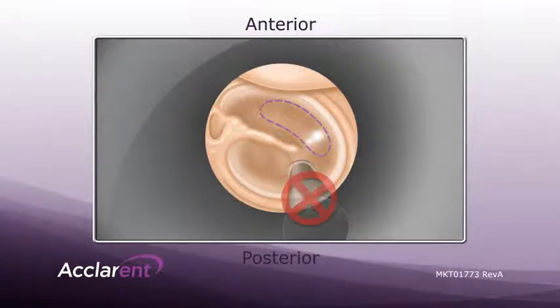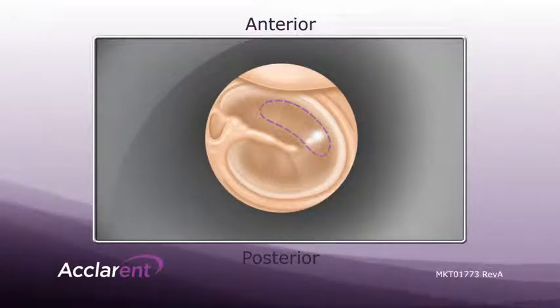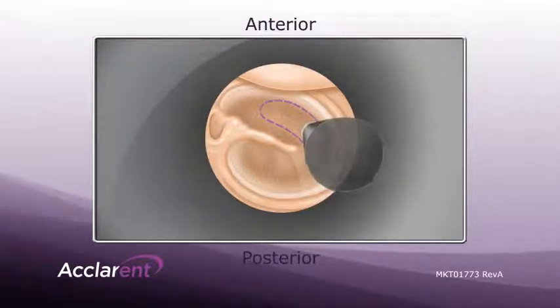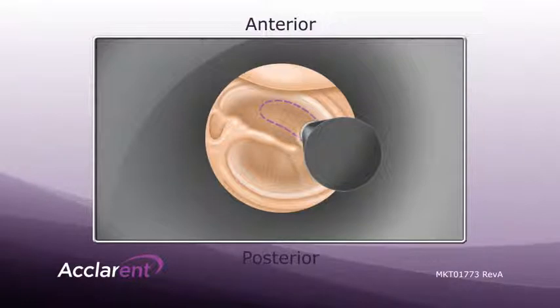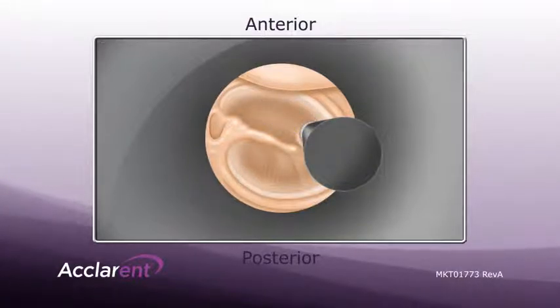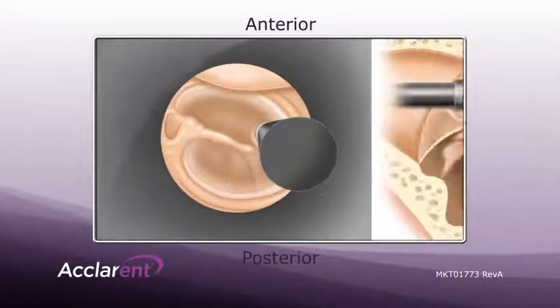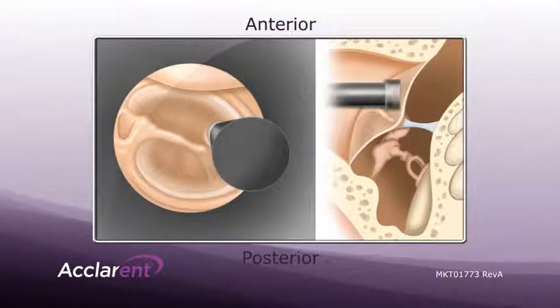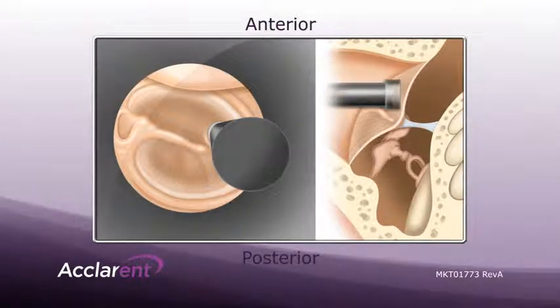For proper deployment of the tympanostomy tube, it is important to achieve circumferential apposition of the device tip against the tympanic membrane. In some cases, such as in a highly angled tympanic membrane, the device tip may contact the TM without achieving circumferential apposition.